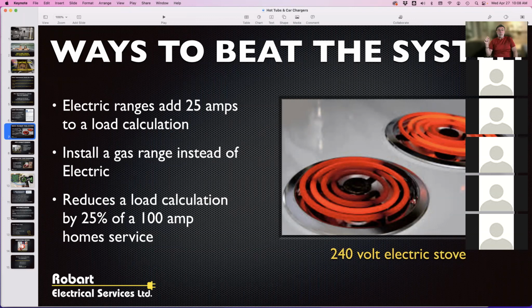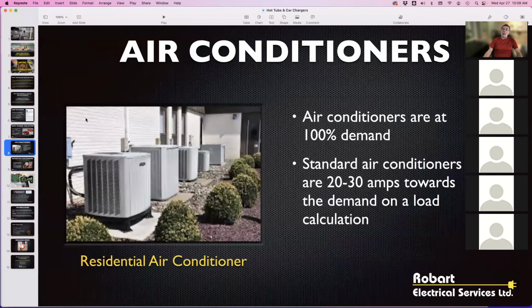25 amps off a 100 amp service reduces it by 25%. Air conditioners are another big one, calculated at 100%. You can look on the nameplate data for the amperage of the air conditioner, but as a rule of thumb, they're usually 20 to 30 amps towards the demand on the load calculation. So if you've exceeded 100 amps in your load calculation and you're trying to reduce it, air conditioners are one of the things putting demand on the system.